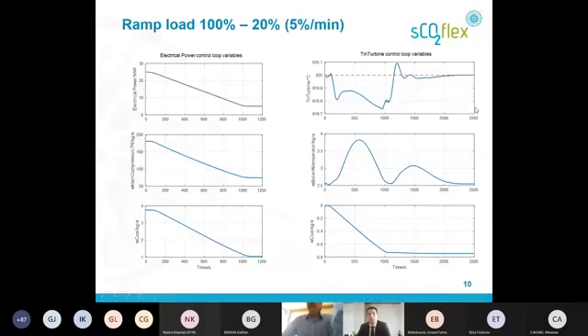And indeed, we demonstrated it with Modelica simulations. These are the results for a ramp load variation from nominal conditions down to 20% of load with a rate of variation of 5% per minute. The dotted lines are referring to the setpoint variables, and the continuous line is the result of the calculation in dynamic conditions. And you can appreciate that the electrical power output is very well followed. We have some oscillations, of course, of some variables.